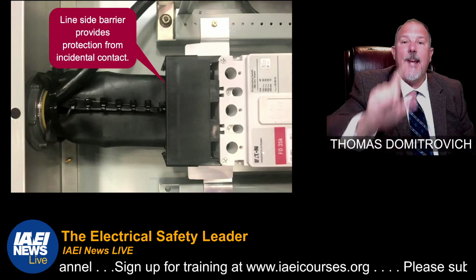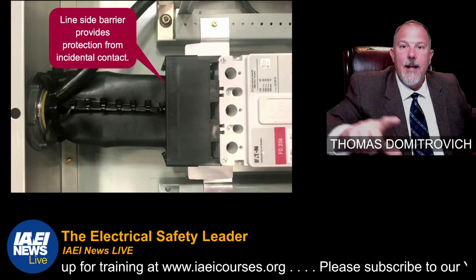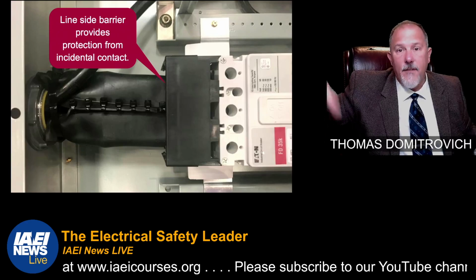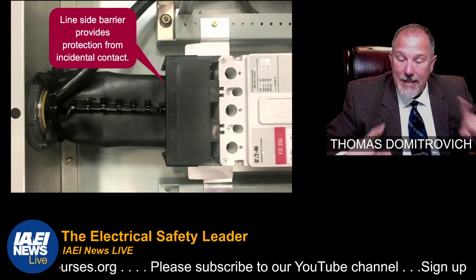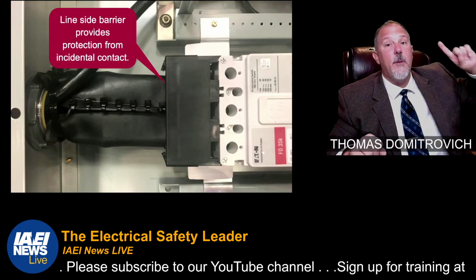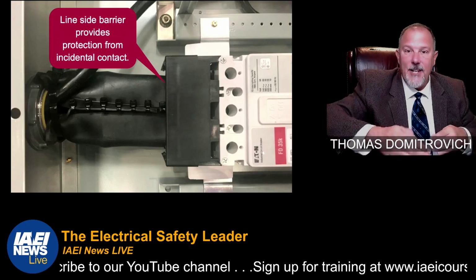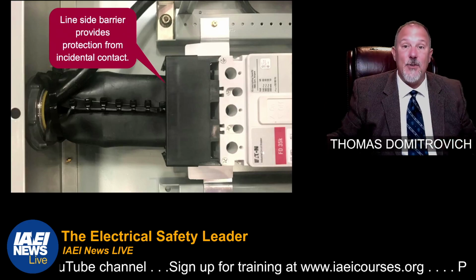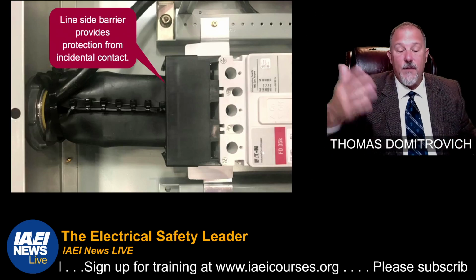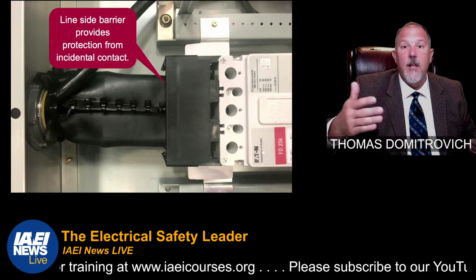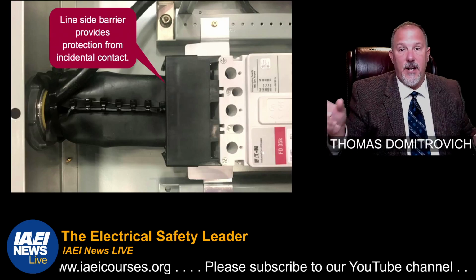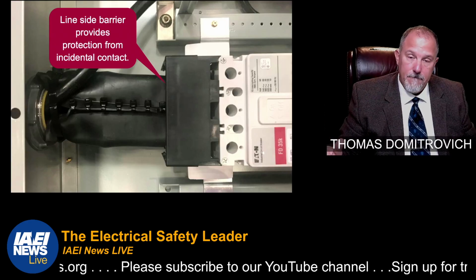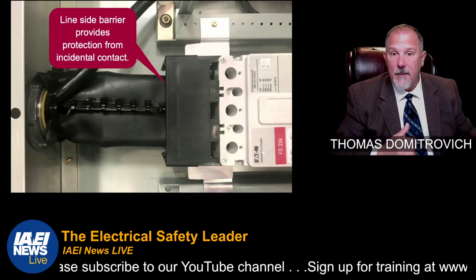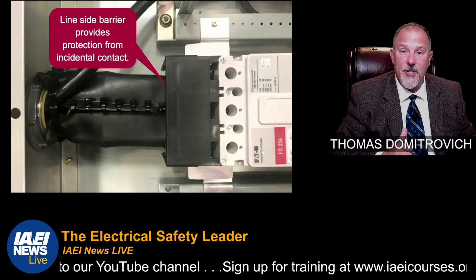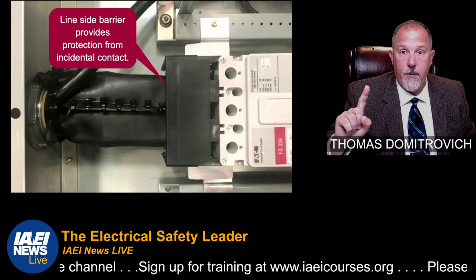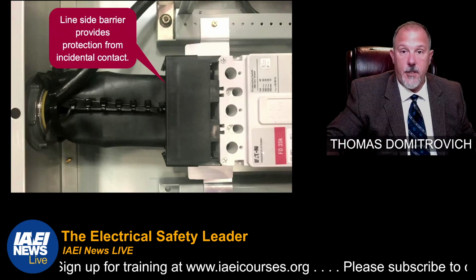And why is that? The incident energy at the service, and on the secondary of every transformer, is high. Why is that? Because the clearing time is based upon the primary overcurrent protective device, which is intentionally inflated in size to handle inrush currents. So I inflate the size of the primary overcurrent device, which puts that device outside of providing arc reduction. It'll put the arcing currents in the long time clearing time, and your incident energy at that first panelboard is true to roof. True to roof. It's a West Virginia term.